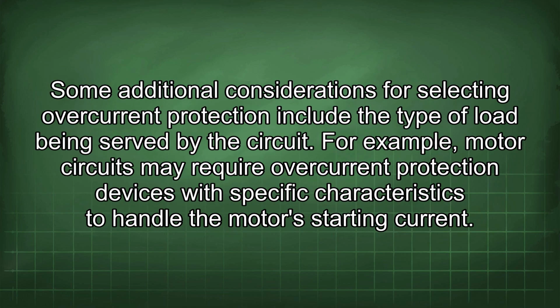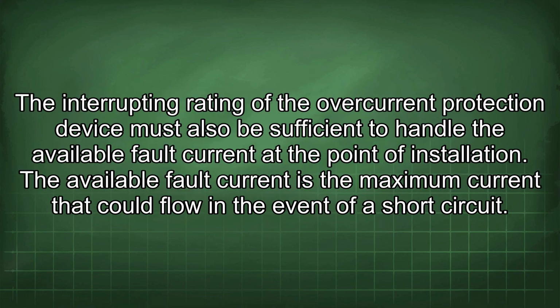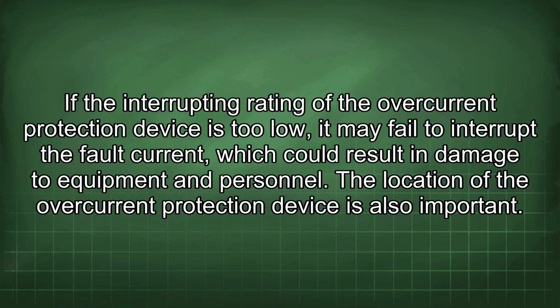Some additional considerations for selecting overcurrent protection include the type of load being served by the circuit. For example, motor circuits may require overcurrent protection devices with specific characteristics to handle the motor's starting current. The interrupting rating of the overcurrent protection device must also be sufficient to handle the available fault current at the point of installation. The available fault current is the maximum current that could flow in the event of a short circuit. If the interrupting rating of the overcurrent protection device is too low, it may fail to interrupt the fault current, which could result in damage to equipment and personnel.